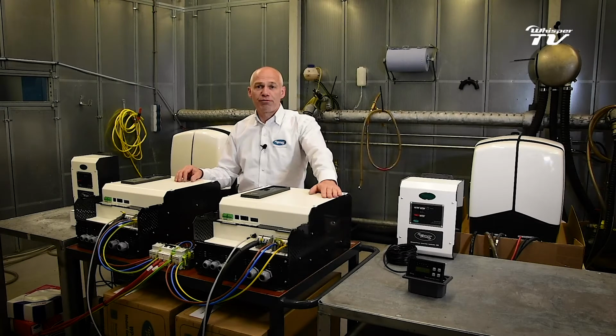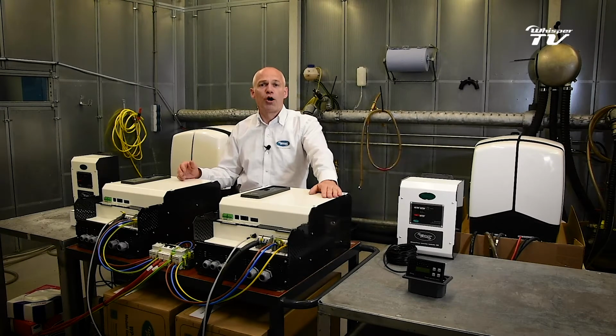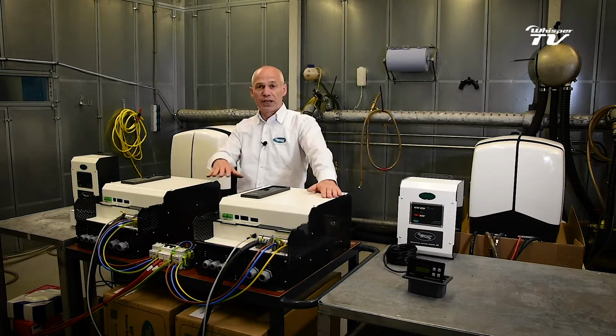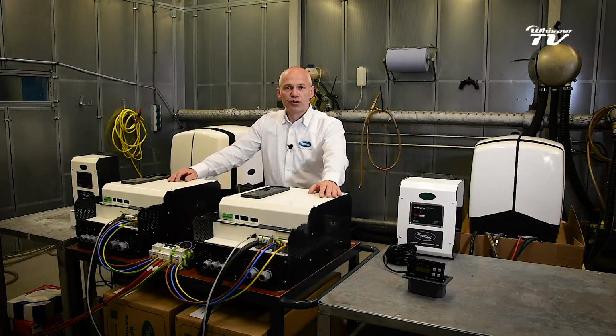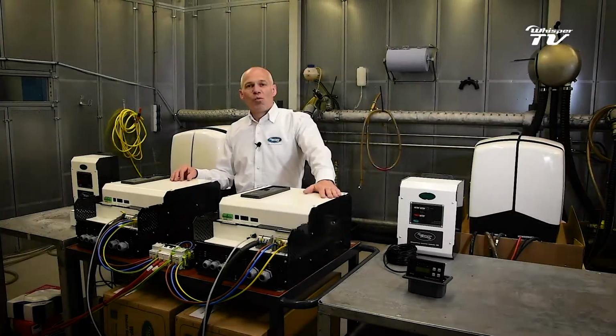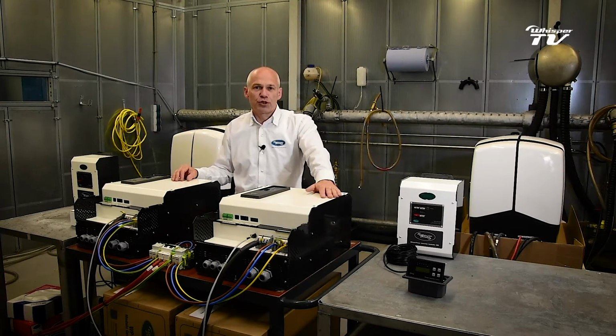In this room we have installed two Genverters of 15 kVA which are fully operational and running in parallel operation. The total electrical power when both units are running at the maximum power is 30 kVA, 230 volt, 50 cycles, single phase. Well, what about the setup of the TwinPower? Is it complex? No, it's not complex. The installation is simple, plug and play.